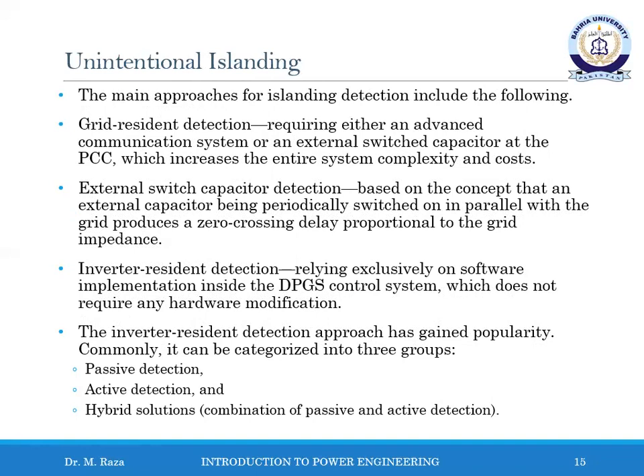External switched capacitor detection method, which is based on the concept that an external capacitor being periodically switched on in parallel with the grid produces a zero crossing delay proportional to the grid impedance. Another approach is called inverter resident detection, which relies exclusively on software implementation inside the distributed generation control system and does not require any hardware modification. The inverter resident detection approach has gained popularity. Commonly, it can be categorized into three groups: passive detection, active detection, and hybrid solution, which is the combination of passive and active detection.